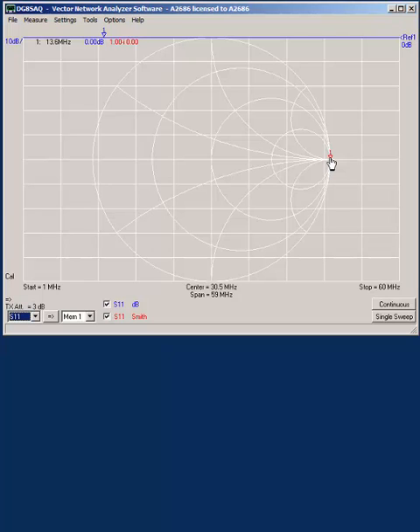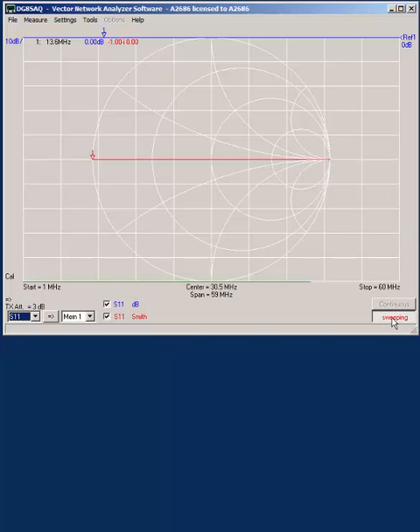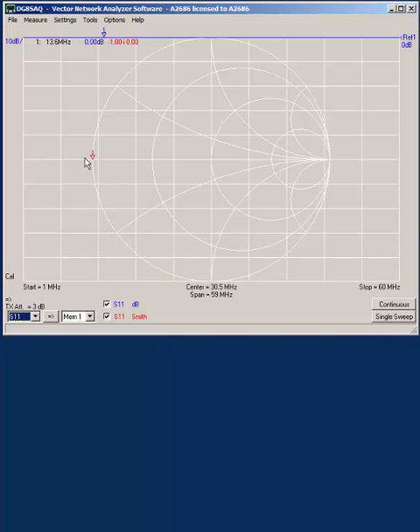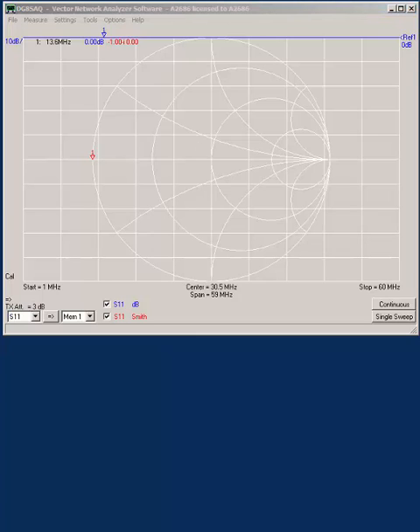The last thing that we would do is connect a short. If we connect the short and do a single sweep, it moves to the left hand side, so now we're assured that the network analyzer is correctly calibrated.